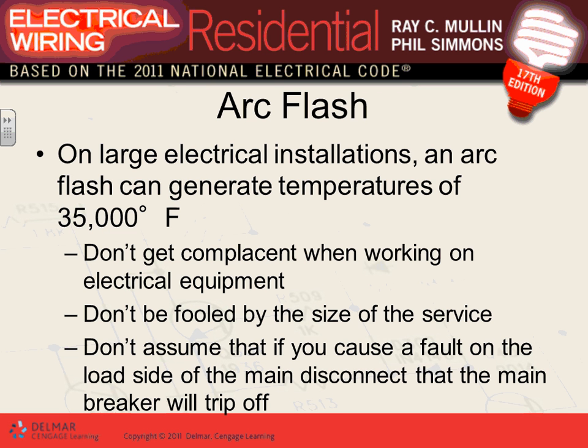How do you verify if something is disconnected? You grab your voltmeter. OSHA and 70E say after you disconnect it and lock it, you are to grab your voltmeter, measure line to line, line to line, line to line, line to ground, line to ground, line to ground, no voltage. Now, this piece of equipment is dead.